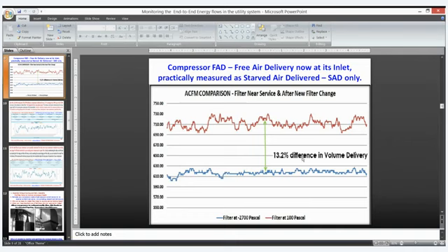This is an area where we have to monitor the filters. You can have an air intake delta P gauge, a magnetic gauge or a digital gauge; everything is available. The console talks in terms of bar, but in pascals, 1 lakh pascal is equal to 1 bar. So you have to monitor the air intake filter in terms of pascals only.